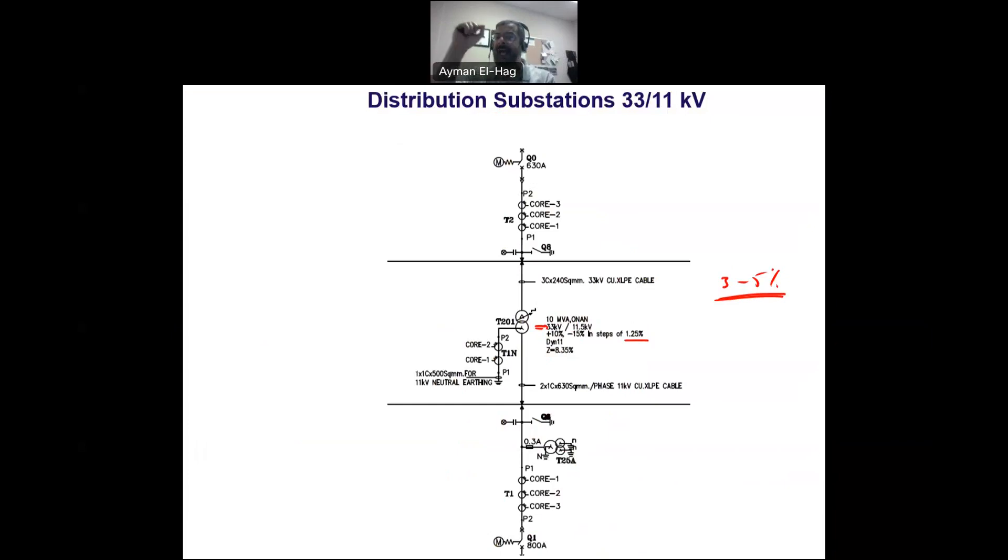We want to maintain the voltage within certain tolerance. Usually, the voltage has to be maintained around 3% to 5% at the 11 kilovolt side. To maintain this, I have to control the voltage whenever there is any change in the load using the tap changer. By increasing or reducing the number of turns, I can increase the voltage up to 10% or reduce it up to 15%, and each step is 1.25% of the rated voltage. This is done using an online or on-load tap changer.